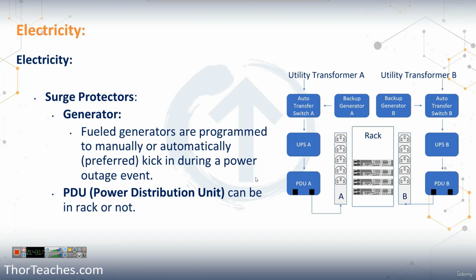The UPS really does nothing - it just sits there and waits until we don't have enough power. Then the battery starts discharging. Once the generator starts, the batteries stop sending power because the systems already get it from the generator, and the battery starts recharging.